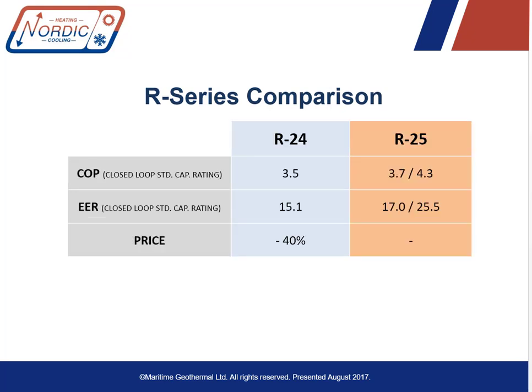For a further comparison of efficiency and price, I'm going to compare the 2-ton model, so the commercial R24 versus the residential R25. The heating COP, so that's the standard heating capacity for a ground loop, which is an AHRI condition for comparing different manufacturers' heat pumps. You can see here the COP is a little bit lower, 3.5 instead of the 3.7 or 4.3 for the 2 stages of operation of the larger unit. And the EER is also a little bit lower, but still quite attractive.